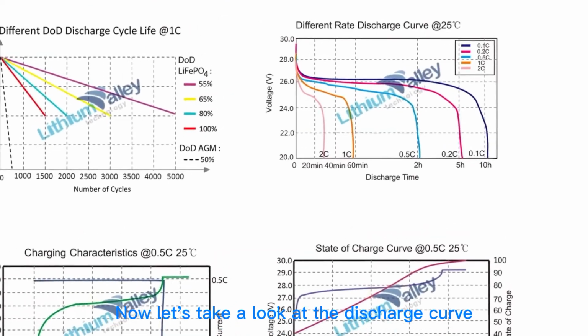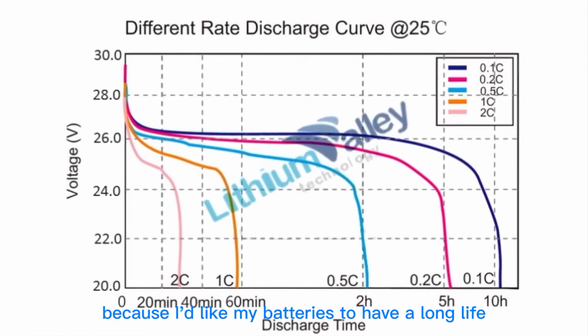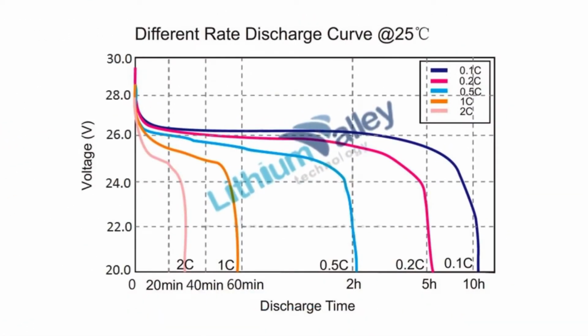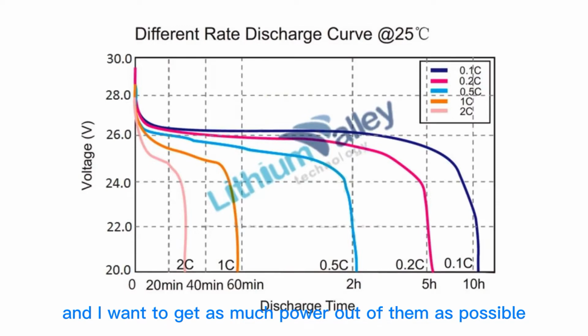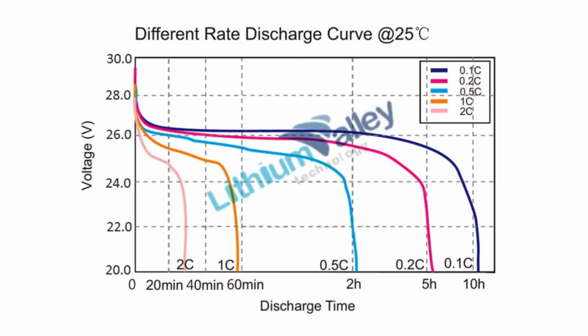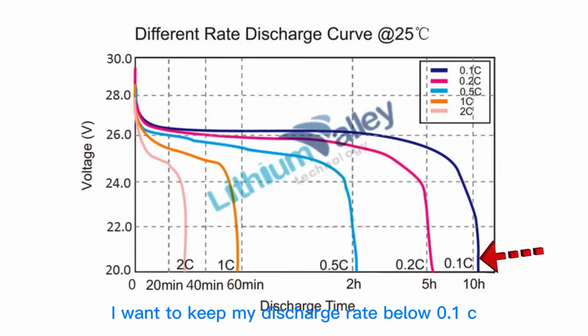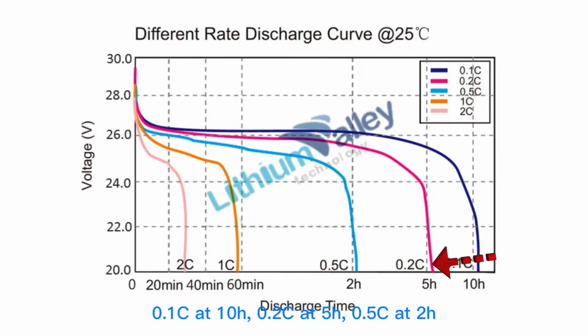Now let's take a look at the discharge curve. Because I'd like my batteries to have a long life, and I want to get as much power out of them as possible, I want to keep my discharge rate below 0.1 C. Now, somebody might look at this graph and go 0.1 C at 10 hours, 0.2 C at 5 hours, 0.5 C at 2 hours. Basically, that's all the same.